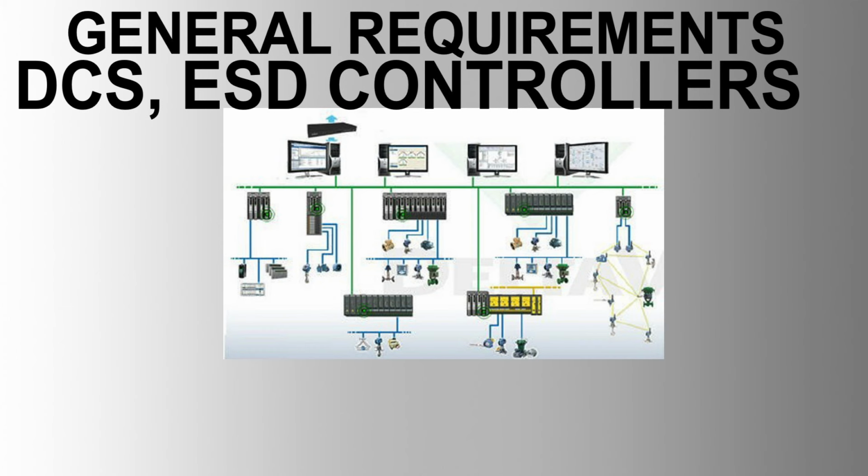circuit as 0. Each input is galvanically isolated from the system and other inputs to 1000 volts DC. Digital output cards provide volt-free contacts capable of withstanding 24 volt DC minimum. Contacts are software selectable SPST-NO or SPST-NC and rated for 2A at 30 volt DC. Replaceable load fusing is provided on an individual channel basis.